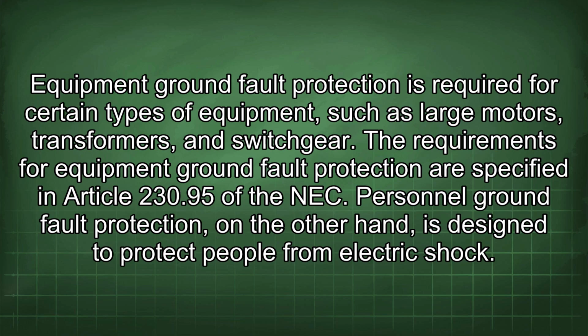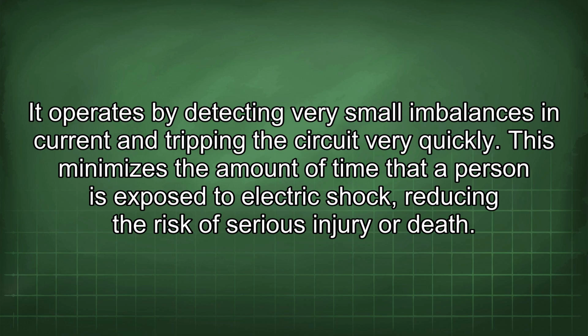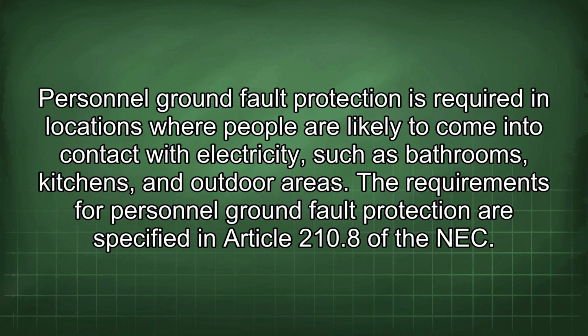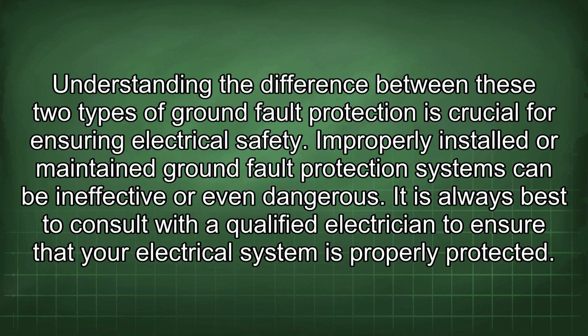Personnel ground fault protection, on the other hand, is designed to protect people from electric shock. It operates by detecting very small imbalances in current and tripping the circuit very quickly. This minimizes the amount of time that a person is exposed to electric shock, reducing the risk of serious injury or death. Personnel ground fault protection is required in locations where people are likely to come into contact with electricity, such as bathrooms, kitchens, and outdoor areas. The requirements for personnel ground fault protection are specified in Article 210.8 of the NEC. Understanding the difference between these two types of ground fault protection is crucial for ensuring electrical safety.